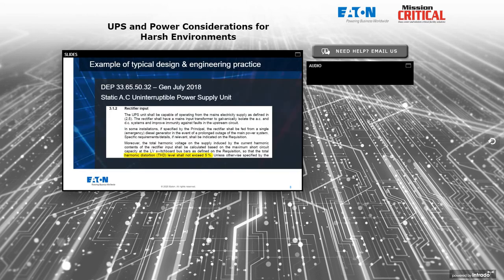Here's an example of a typical specification, and the part that's highlighted here is the input harmonic distortion. In other words, the harmonic distortion that the UPS system rectifier throws back on the source that feeds it. In highly industrial applications, distortion is common. We don't want the UPS to contribute unnecessarily to the distortion in the building, because that can impact other loads that don't happen to be on the output of the UPS. So the requirement commonly in the US is that input distortion, or THD for total harmonic distortion, must not exceed 5%.